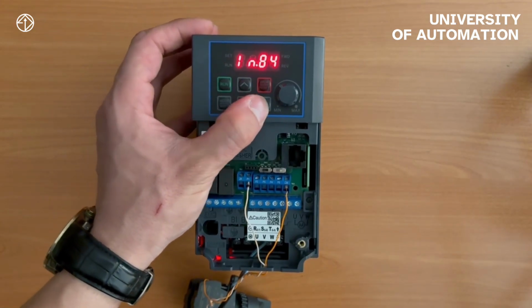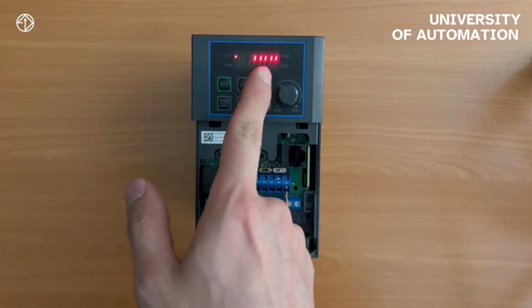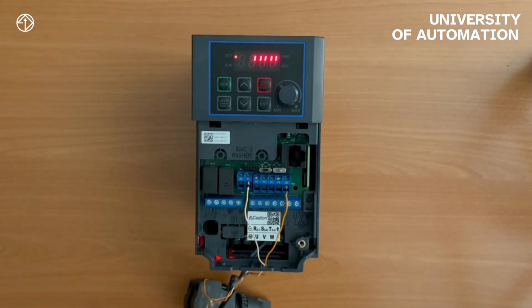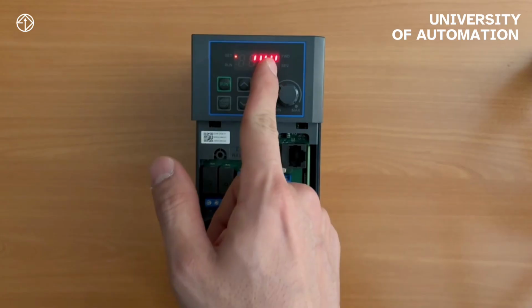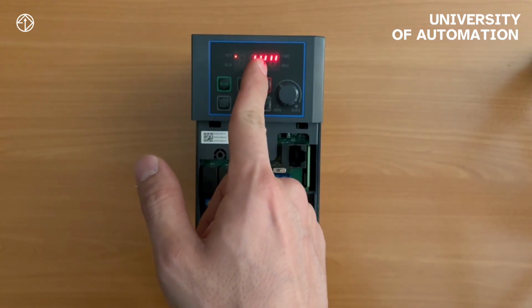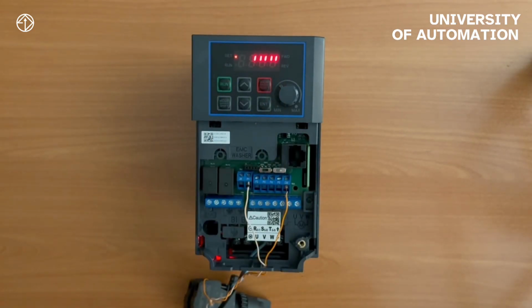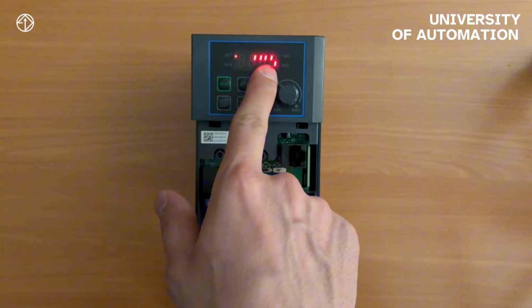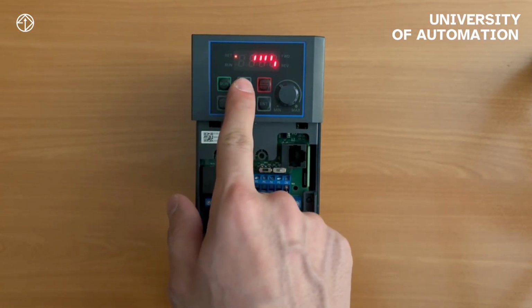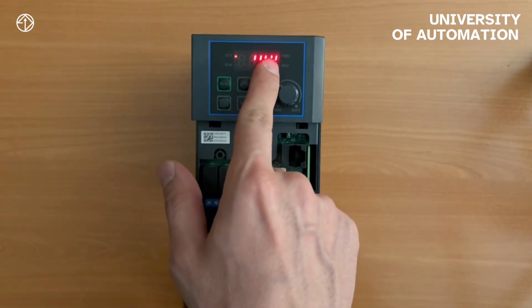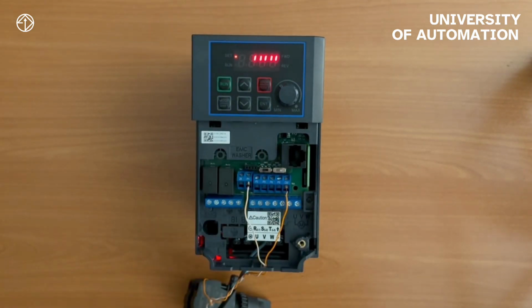When we enter parameter 84, as we said, it displays 5 bits for us. Each of these bits corresponds to one of the digital inputs. The first bit is for P1, then P2, P3, P4, and P5. If these bits are set to high, the filter or delay for that digital input is active, and if they're set to low, for example, right now I've set the bit for P1 to low. Low means its filter or delay time is deactivated. If I set it high again, it activates. So each of these bits corresponds to one of the digital inputs.